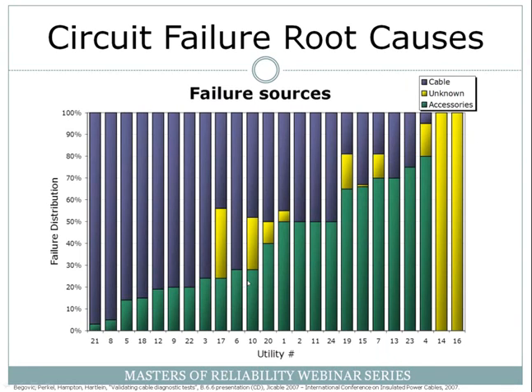The paper that the following graph comes from was presented at the Jicable conference in Versailles, France in 2007. It's some NEETRAC data — they polled over 20 circuit owners and determined the causes of failures. For example, circuit owner number 21 found they had predominantly cable failures, whereas circuit owner number 4 had predominantly component failures. If you average all those together, you get about 39% accessory failures, about 55% cable failures, and about 6% unknown.